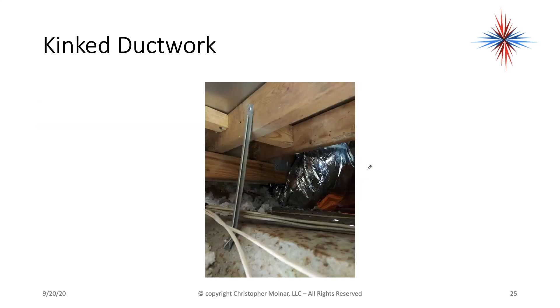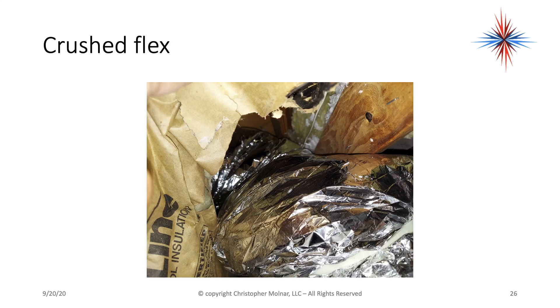One of the issues is kinked duct work. If you look closely at this picture here, you'll see that they've pulled it below a joist and clamped it between the ceiling and the joist — this is a suspended ceiling. It's cut the duct work flow to about a third of what it's supposed to be. Crushed duct work is another issue. Flex duct can't have this crushed area because it restricts airflow. Flex duct is supposed to be pulled tight and supported — it's not supposed to be kinked, crushed, and bent.